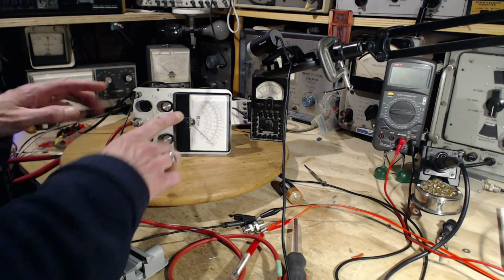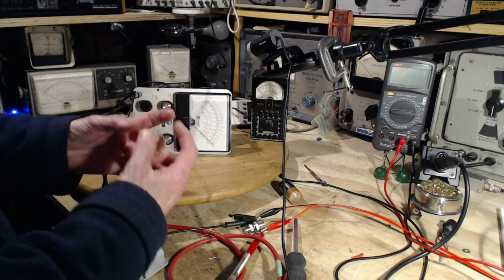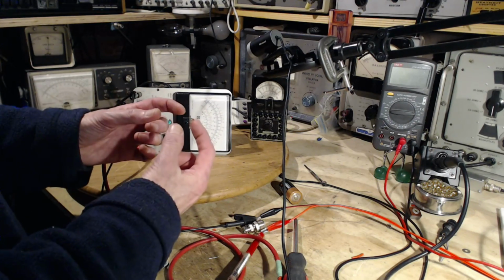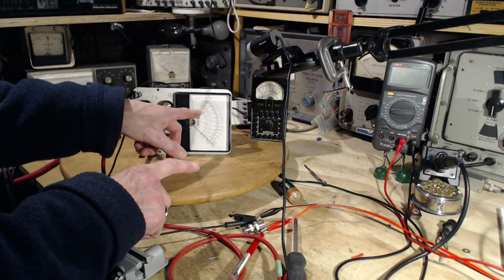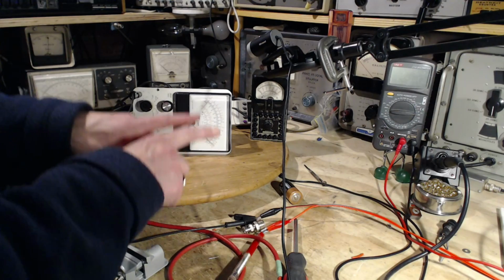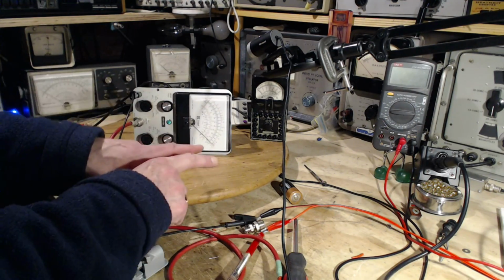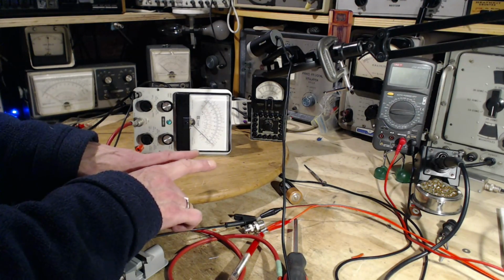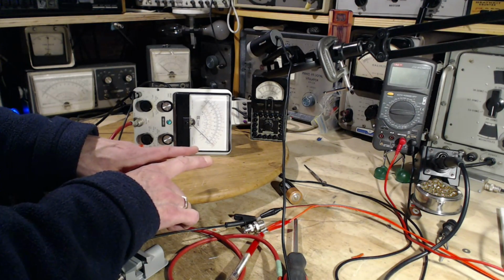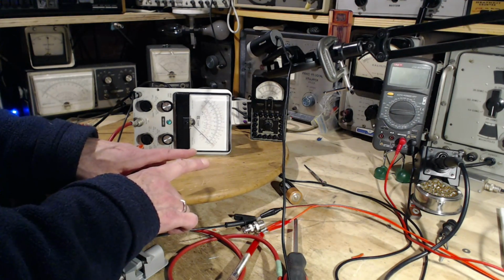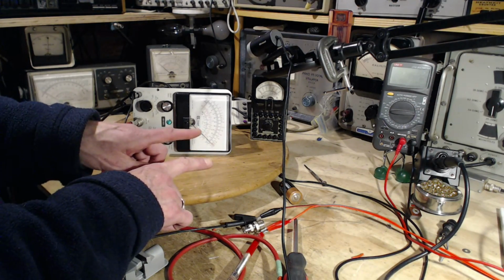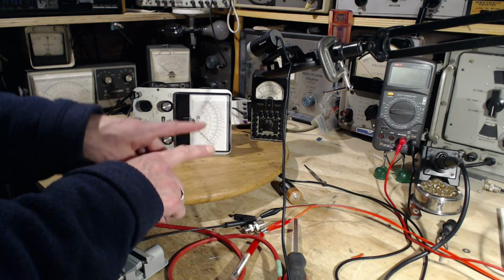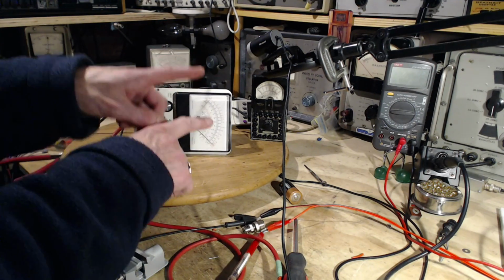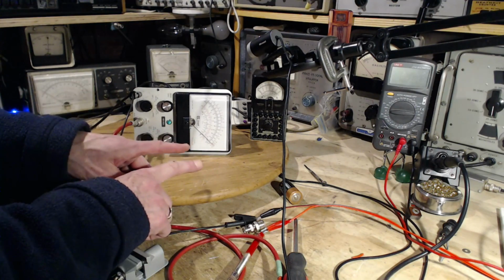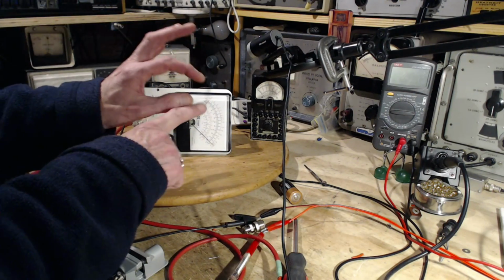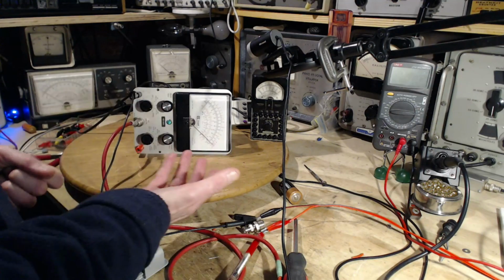The meter reads the difference between the cathode potentials, or something, in the cathode circuits of the two sections of the 12AU7 tube. So if the two cathode voltages, the points where this movement is connected, exhibit a common mode voltage, then the meter sees nothing, and it will just sit on 0. And so the idea is the incoming signal is conditioned and used in such a way as to raise, I'm not sure if it's one or both of the voltages here. If it raises one, there's a difference voltage that the meter will see. But it could even raise two in a proportional manner. I'm not sure. But all of it is sort of held arithmetically to being proportional. So the difference in the voltage still proportionally reflects the voltage coming in or being tested.